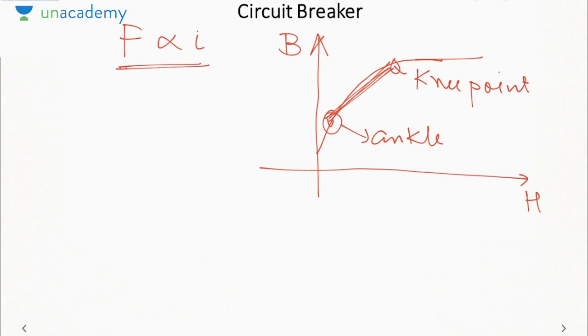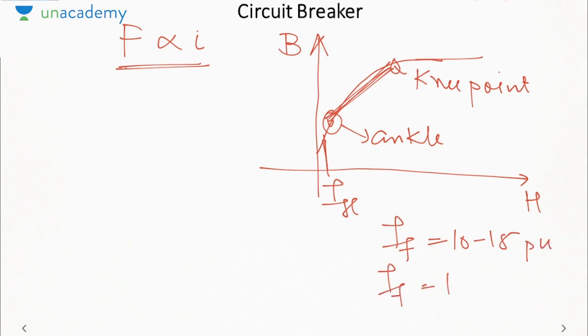Due to this, I always want to operate in the linear region. So the normal operating point should be here, that is IFL, so that whenever a fault occurs, usually the fault current is 10 pu, 15 pu, or we can say the fault current is 10 to 15 times IFL. So if you go to 10 to 15 times, you will land in the linear region.